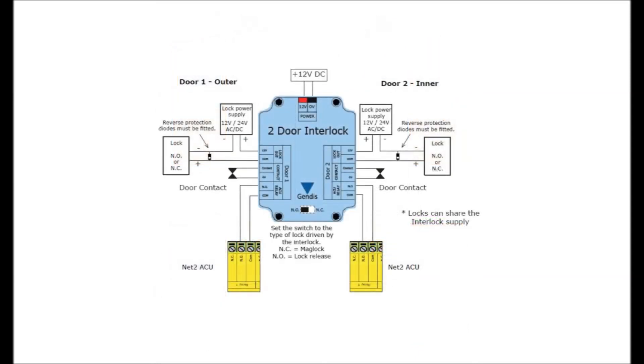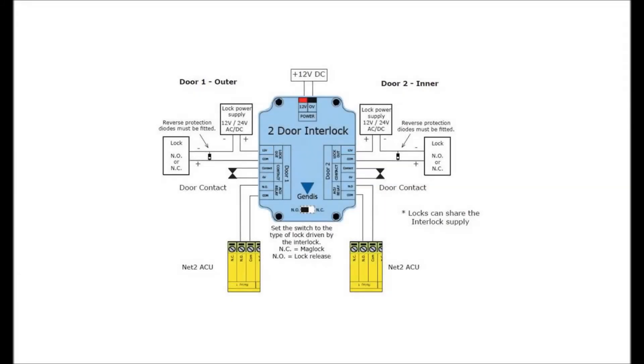Taking a closer look at the interlock again, we can see how the device is laid out. On both door 1 and door 2, it is worth noting that the 12V label refers to the connection of 12V or 24V from the lock, rather than there actually being 12V present at that location. In relation to this, you can use a 24V lock, but you will need 12V for the interlock unit power.